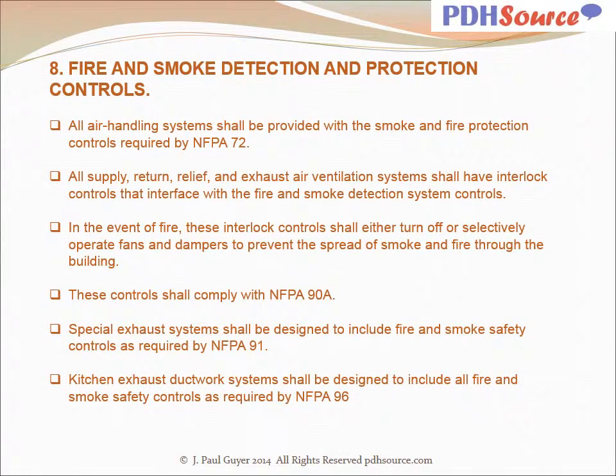All air handling systems shall be provided with smoke and fire protection controls required by NFPA 72. All supply, return, relief, and exhaust air ventilation systems shall have interlock controls that interface with the fire and smoke detection system controls. In the event of fire, these interlock controls shall either turn off or selectively operate fans and dampers to prevent the spread of smoke and fire through the building. These controls shall comply with NFPA 90A.